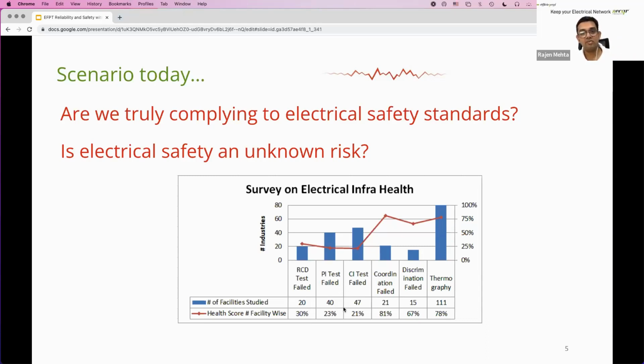Primary injection test — not a very regularly conducted test, a primary or secondary injection test on breakers and relays. But we found that 23% of almost 40 facilities in this survey — we've done hundreds, but selected a sample set across different industries — had breakers or relays that were not tripping as per their supposed time current characteristics.